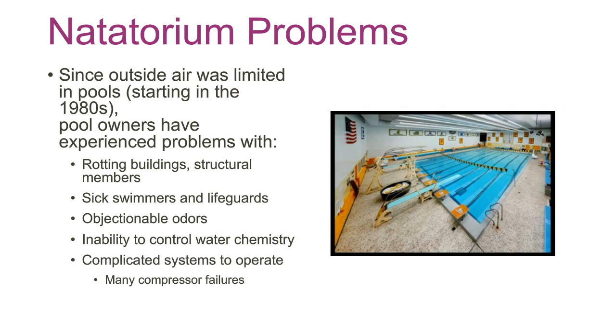So some of the issues that have arisen since about the mid-'80s, when outside air was kind of limited due to energy embargo, was that the buildings were rotting out and had structural problems. You had the sick swimmers and lifeguards. Objectionable odors. If you smell the pool in the hotel lobby, that can tell you, A, that you've got a lot of chloramines out there, and B, that your water chemistry is out of control. And B, the systems that were there were fairly complicated to operate. There was a lot of mechanical failures.